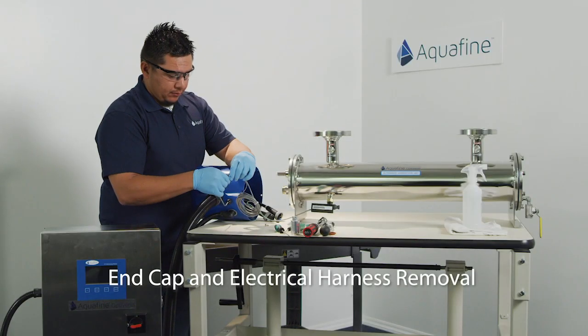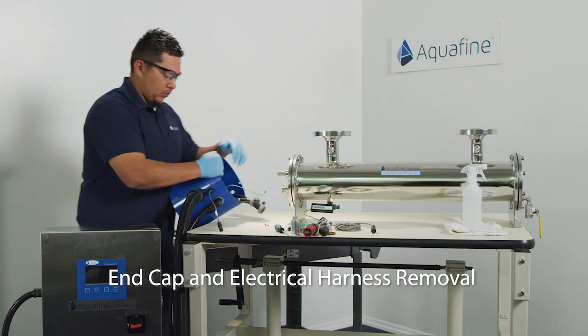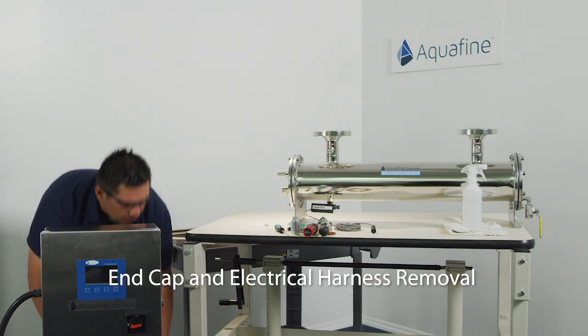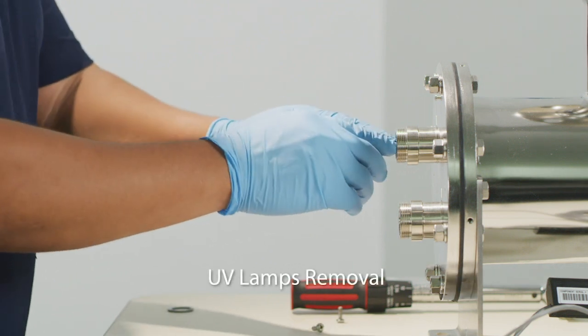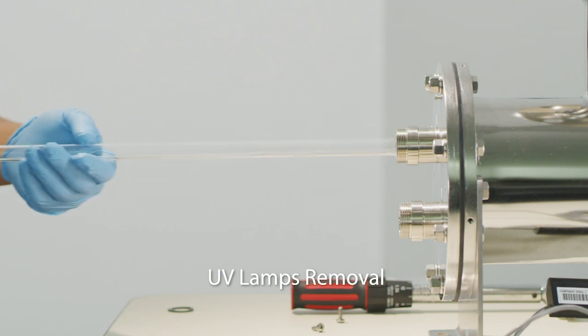With all electrical connections freed from the end of the UV treatment chamber, the end cap and electrical harness can be removed and placed away from the end of the treatment chamber. The UV lamps can be removed out of the treatment chamber by sliding the lamps out of the quartz sleeve using the compression nut tool provided with the Opti-Ven and an on-site 3/8 inch ratchet.